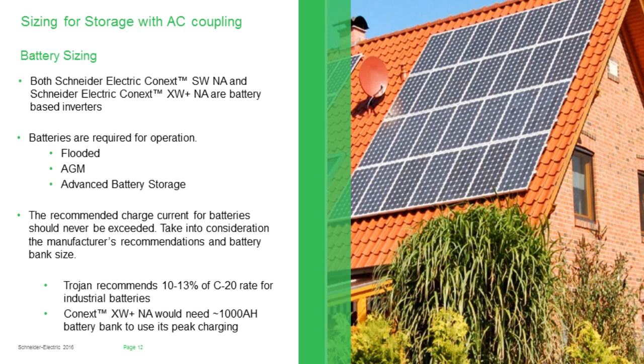One of the things that I strongly advocate for when talking about an AC coupled solution is that there's an assumption for most installs, and that's this: it's going to be connected to the grid 99.99% of the time. So what we're talking about is just a few days out of the year or less where that system is actually going to be called upon to do this AC coupling solution, where the grid forming inverter is interacting with the grid following inverter, or the PV inverter. So I typically recommend choosing a float battery, a battery that's actually made to just hang out and sit on float. The one downside, of course, is that we don't get as many cycles. The upside is that we can actually cycle the system as though we're doing nearly 100% depth of discharge.